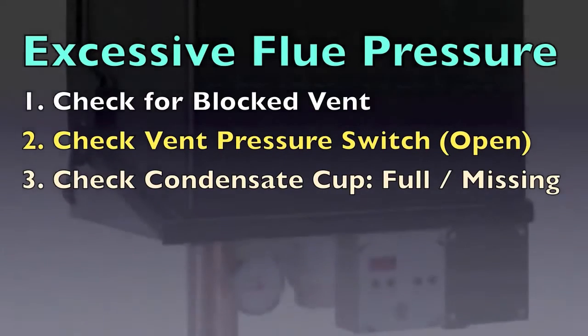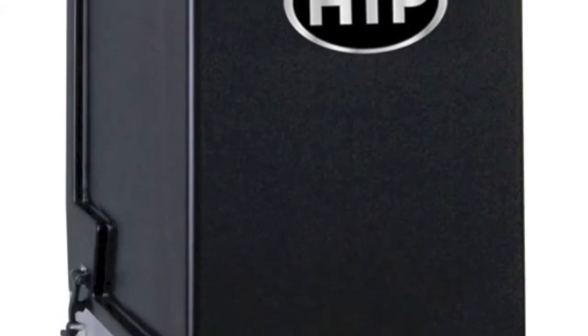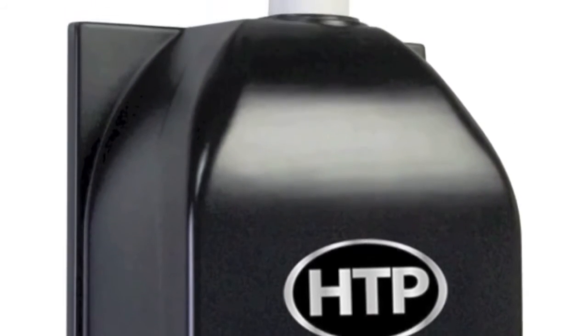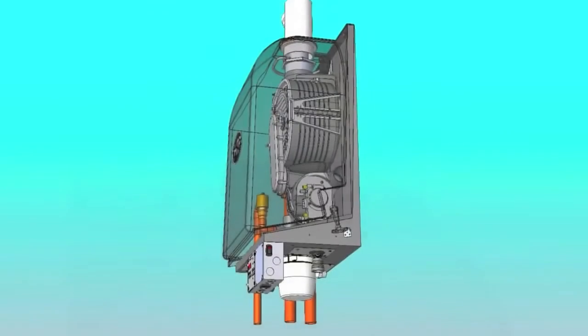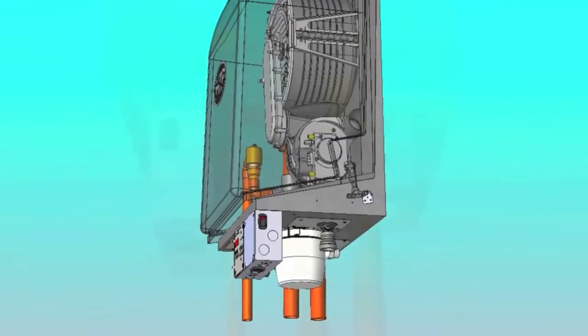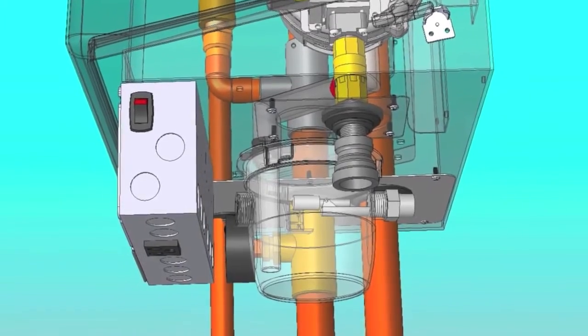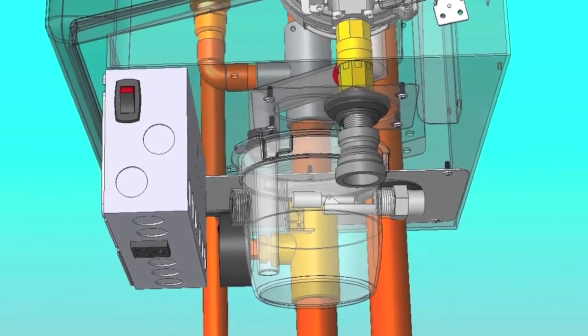If you are getting this code on the MC boilers, first check the vent for blockage, and also check the level of water in the condensate cup to assure that the float switch has not engaged. Also check that the engagement switch on the condensate cup is in the locked position.